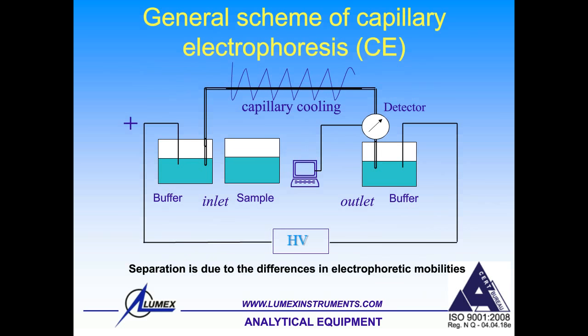Let me now shortly explain how capillary electrophoresis works as a method. The heart of the system is the capillary — a narrow fused silica capillary filled with just a buffer, a plain buffer. It can be borate buffer, phosphate buffer, citrate, or whatever. The capillary is thermostated. There are two ends: the inlet and the outlet, and the detector point is placed near the outlet. The capillary is like a column compared to liquid chromatography, but the difference is that the capillary does not contain any solid sorbents — it contains just a buffer.